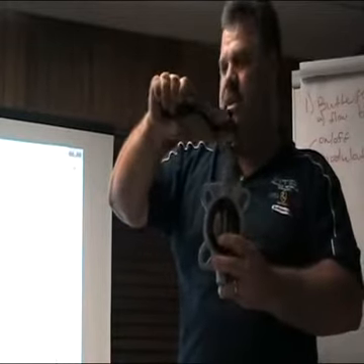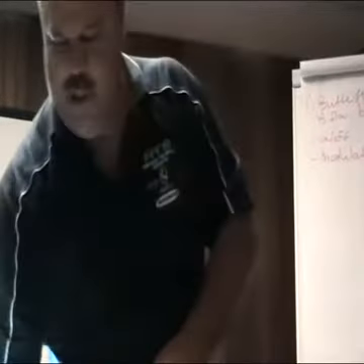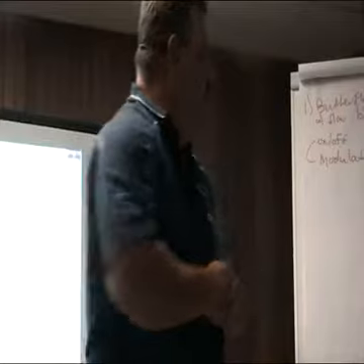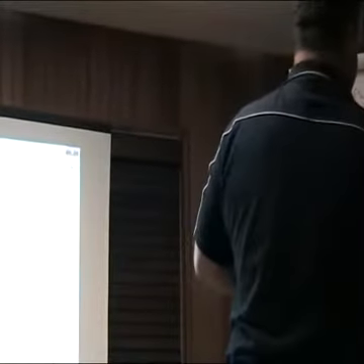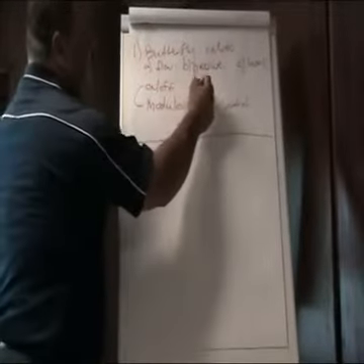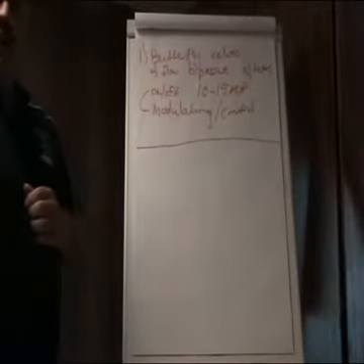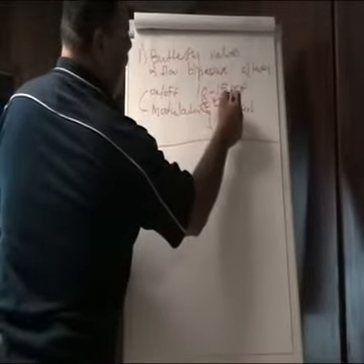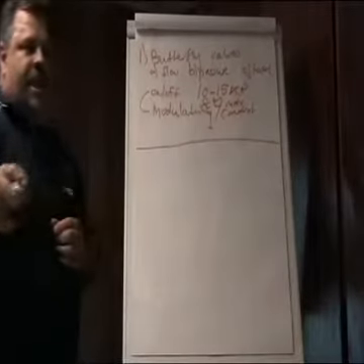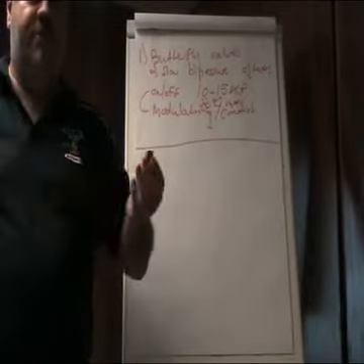No questions in here? Okay, so let's get now to the next one, which we said earlier on when David said something. The high pressure side of it. Okay, we've handled butterflies pretty much. You can do this, but you're limited to 10 to 15 bar. And also, sorry, on the liners, it depends on your liners that you've put in there, that rubber liners. Usually those things can take 80 degrees Celsius, max. Change that liner to PTFE. A lot of those differ. Some guys say 180, some guys say 200, some say 220. I work on average usually about 200 degrees on PTFE.